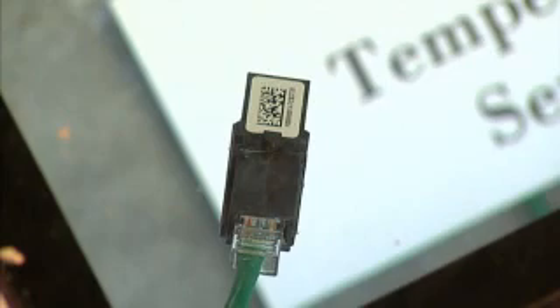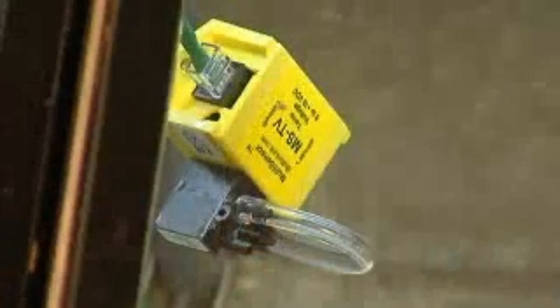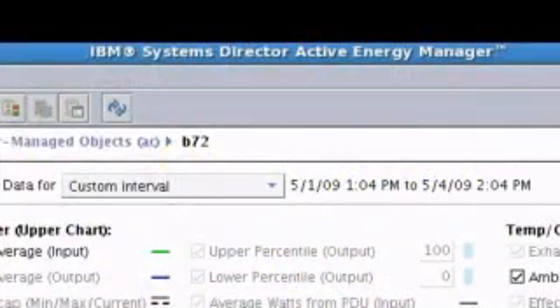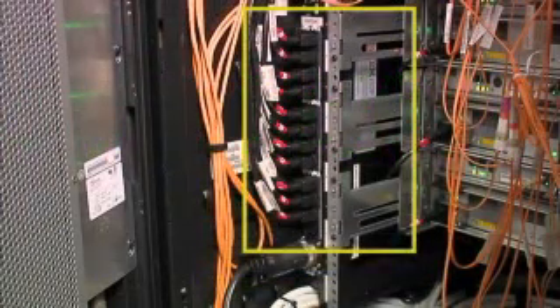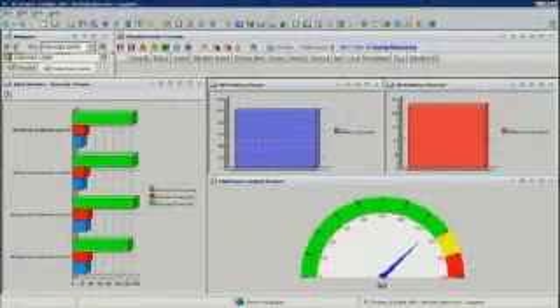One of the things that we wanted to do in making changes to the room was to understand exactly how all the equipment was running. The first thing we did was install thermal sensors that would gather for us the temperature, barometric pressure, and humidity of various areas within the room. We also feed that directly into Director AEM along with the energy consumption, either taking the metrics directly from the servers within the room or using power distribution units, commonly referred to as PDU pluses. In addition, we're using Tivoli products like NetCool Omnibus to gather events and surfacing all of this up into a Tivoli Enterprise portal, which is part of the ITM product suite. This dashboard gives us the latest information of what's happening in the room so we can make adjustments where necessary and plan for future expansion and use of additional hardware.